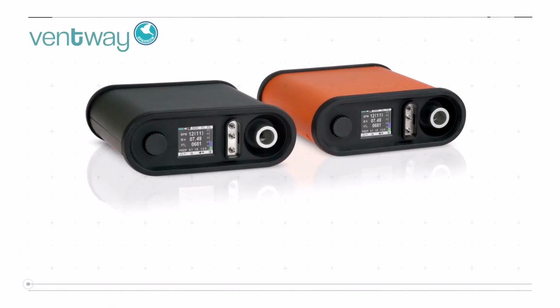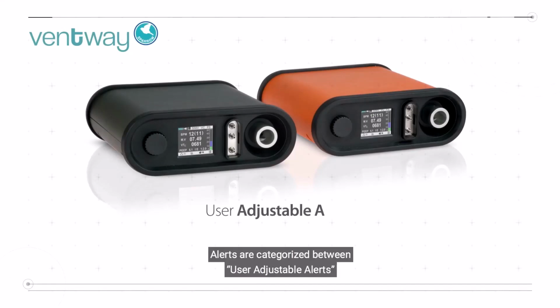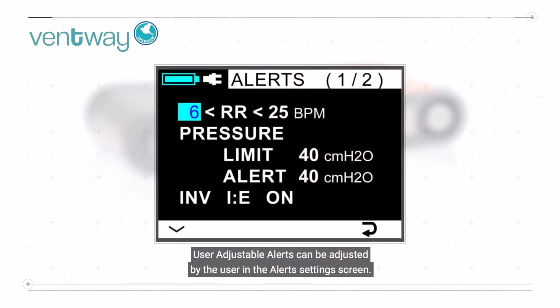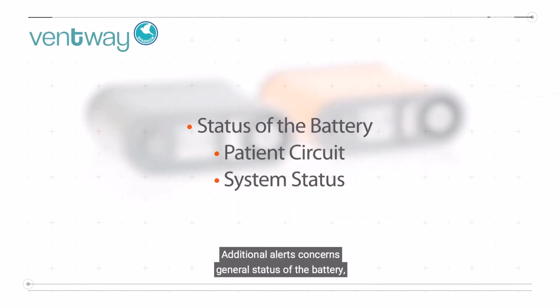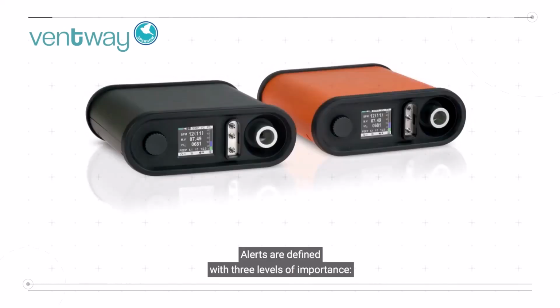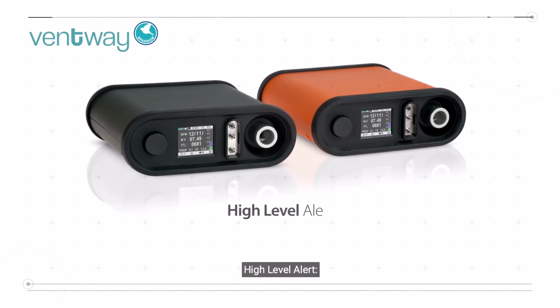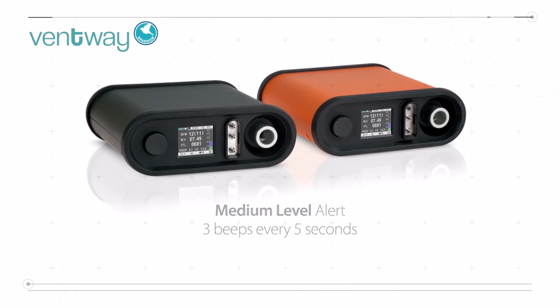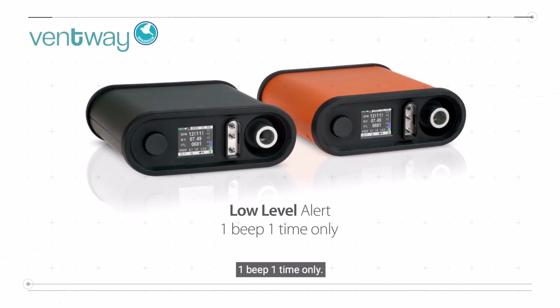Alert settings. Alerts are categorized between user-adjustable alerts and additional alerts. User-adjustable alerts can be adjusted by the user in the Alert Settings screen. Additional alerts concern general status of the battery, patient circuit, and system status. Alerts are defined with 3 levels of importance: high, medium, and low. A different voice indication will be heard for each level. High-level alert: 5 beeps every 2 seconds. Medium-level alert: 3 beeps every 5 seconds. Low-level alert: 1 beep 1 time only.